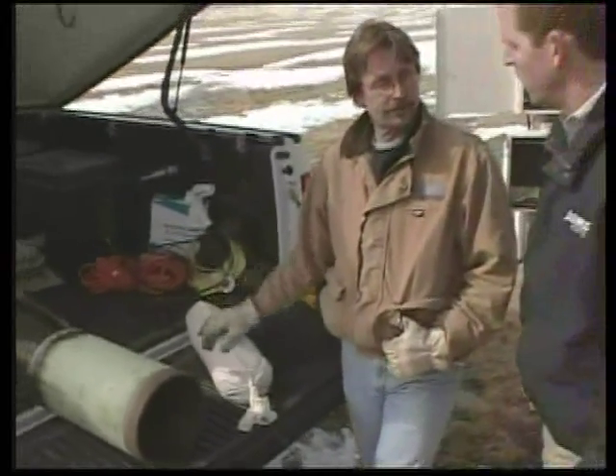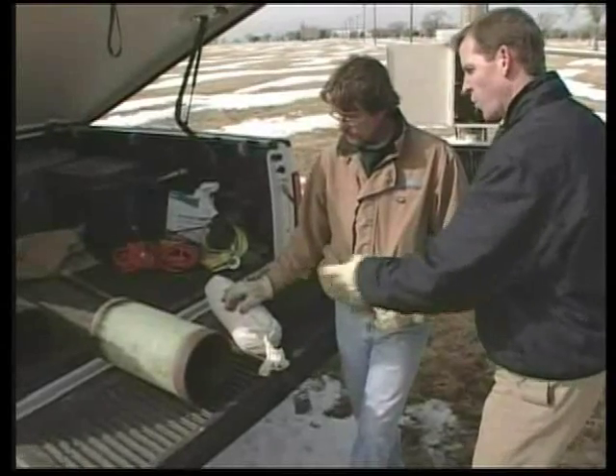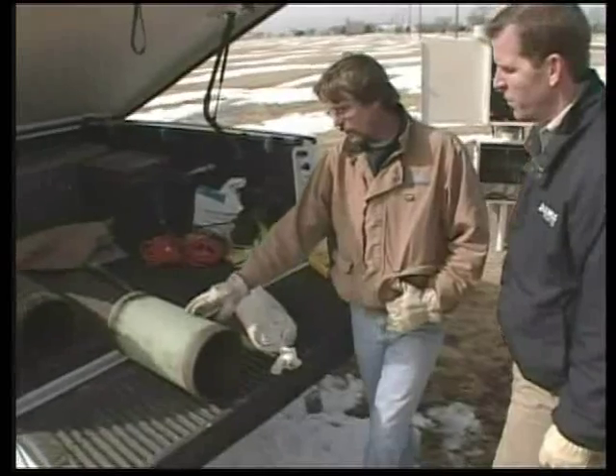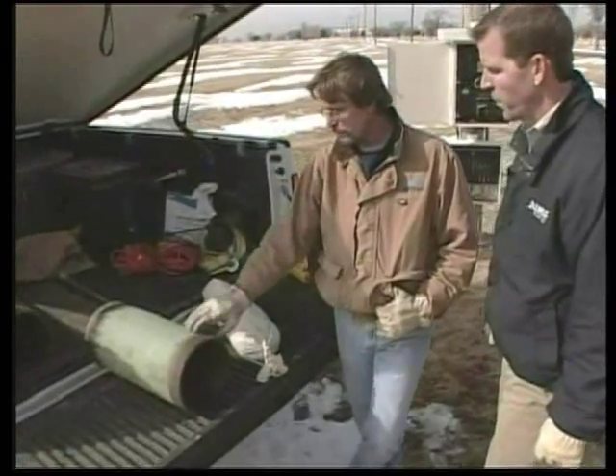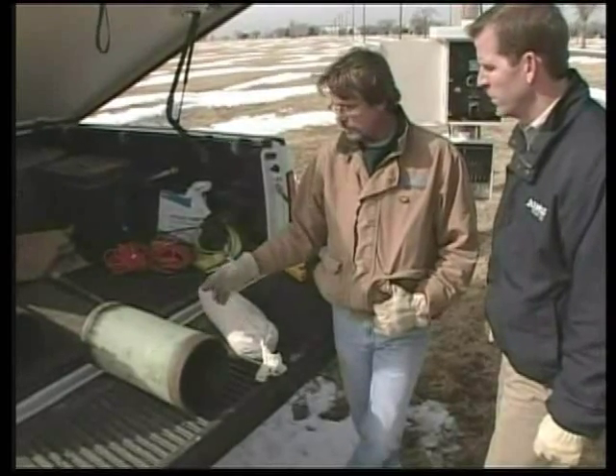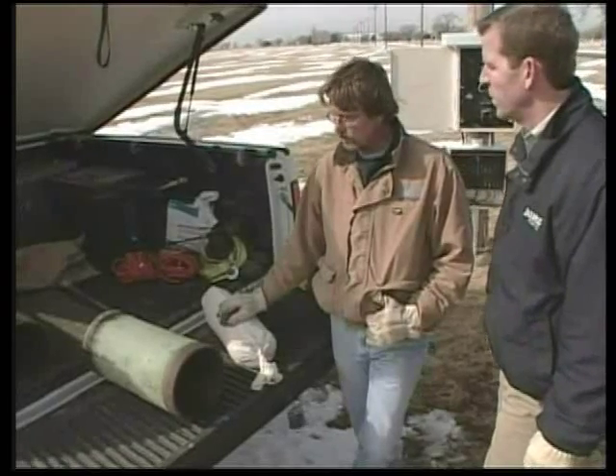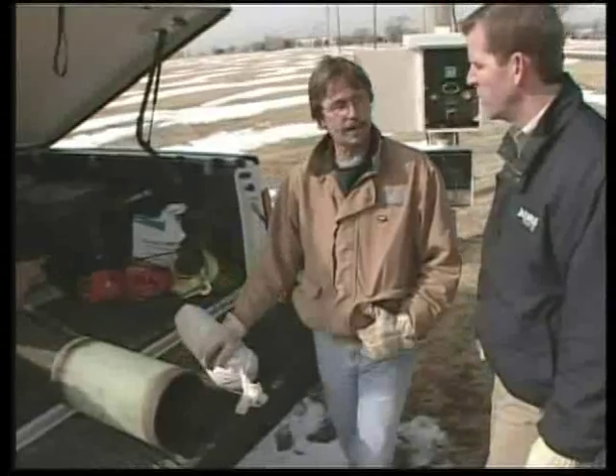So this pipe has coating on it — why does it need cathodic protection? Even though coating probably gives it 90% of the protection, there are always imperfections from the coating plant, and damage when it's shipped, handled, and installed into the ditch. So the cathodic protection is actually concentrating on protecting those exposed places on the pipe.